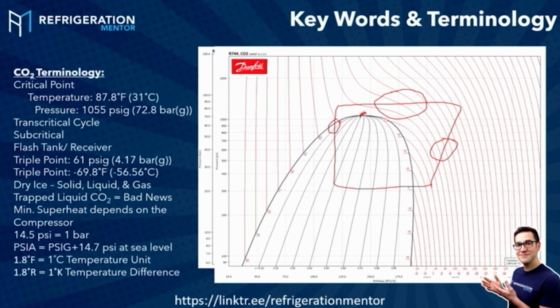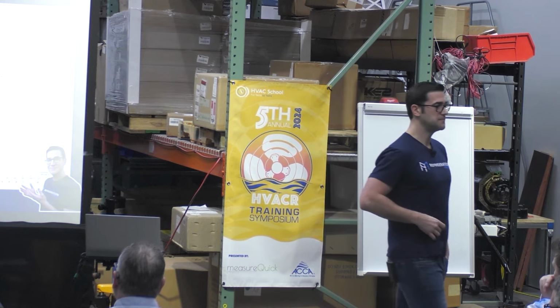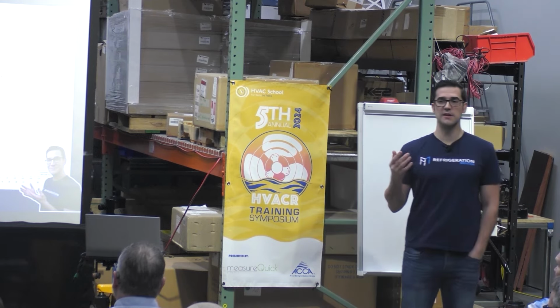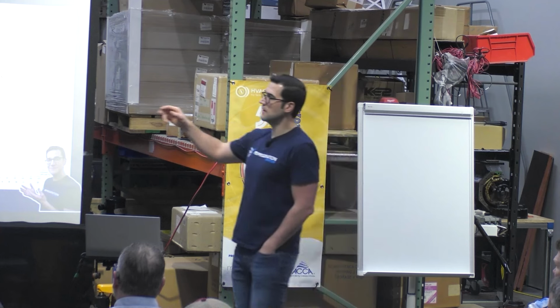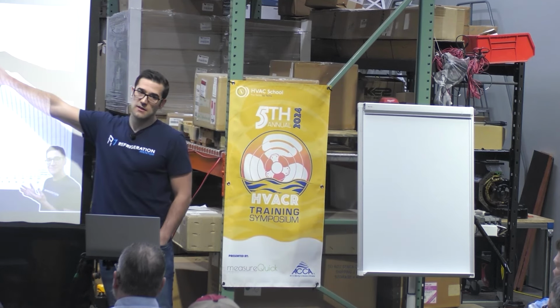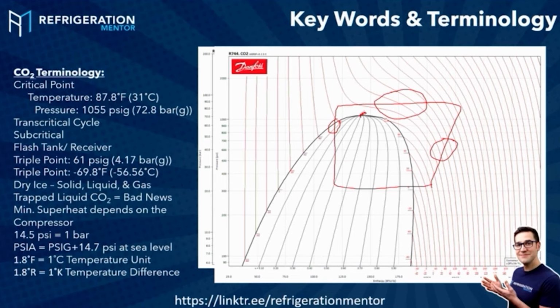And then we have flow back to the medium temp compressor. So what does this all mean? The biggest thing that you need to understand is that this condenser right here does not condense. So they call it a gas cooler. So now all we're doing is cooling the refrigerant.